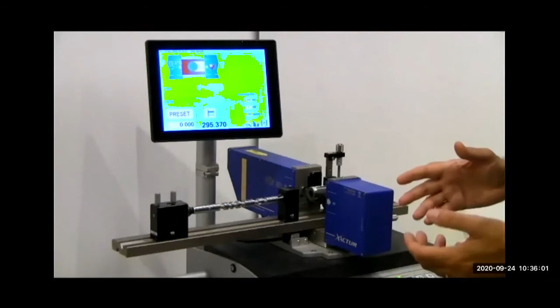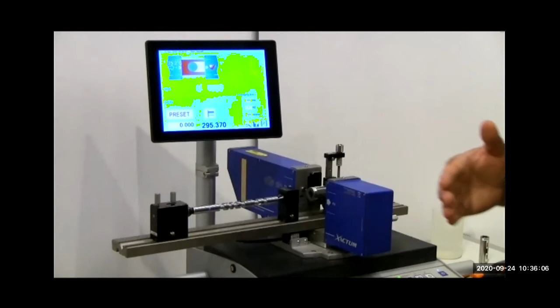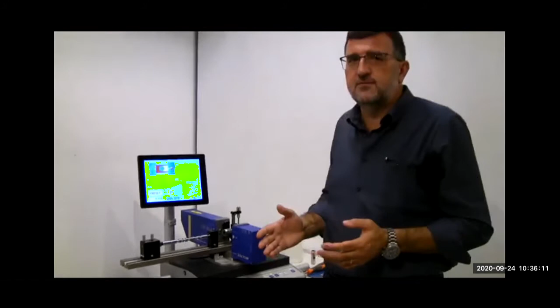So this check can be made directly by the customer, and the calibration can be needed if the customer wants it, because the Italian metrology chain can be a little different from the American metrology chain. Also our calibration masters have an error, normally plus or minus 0.3 microns, an error that we add to the linearity of our product. If the customer has various plants or various systems and wants to calibrate with this set of masters, he can calibrate by himself, surely with the care that this type of operation needs.